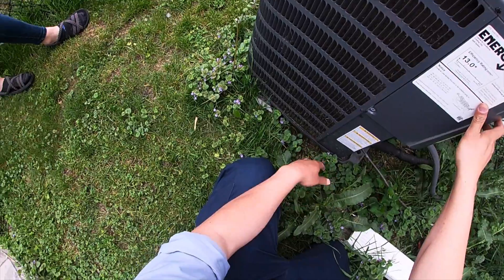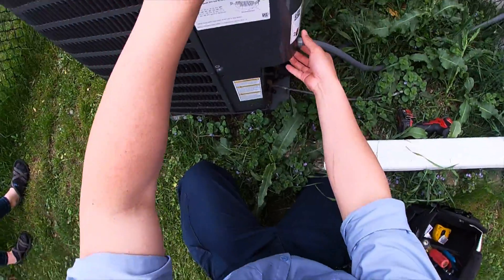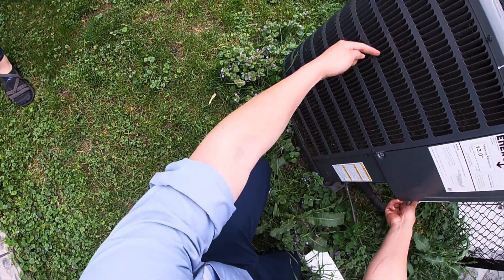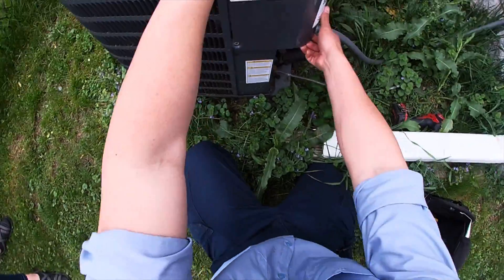It's dirty on the coil. That's not good for the condenser. Because you know the condenser, they reject the heat. If you see it's dirty and they cannot reject the heat, it's not good for the condenser.